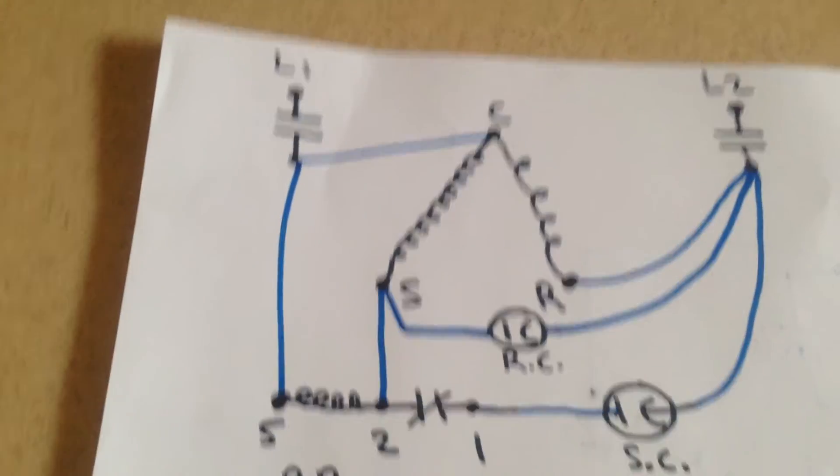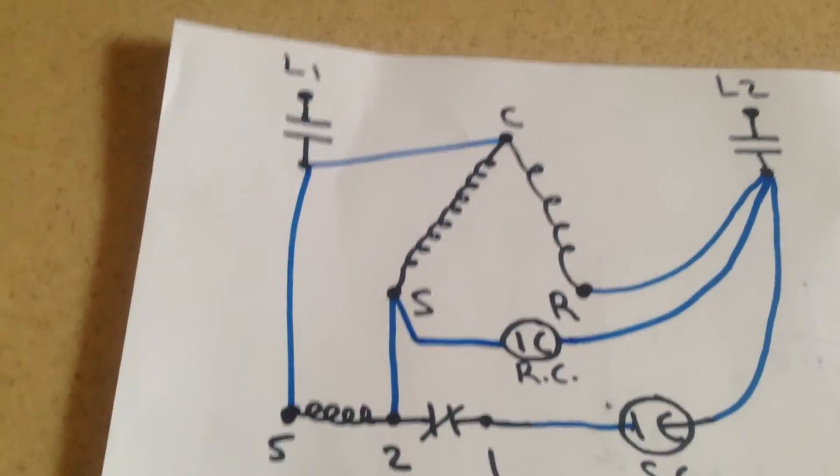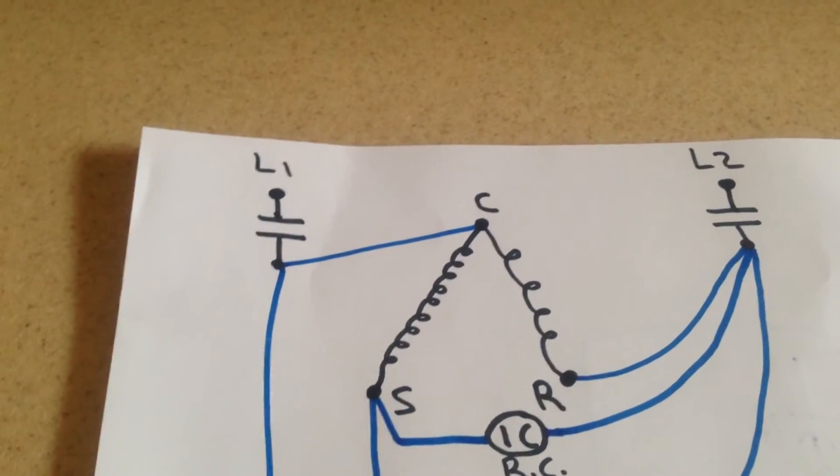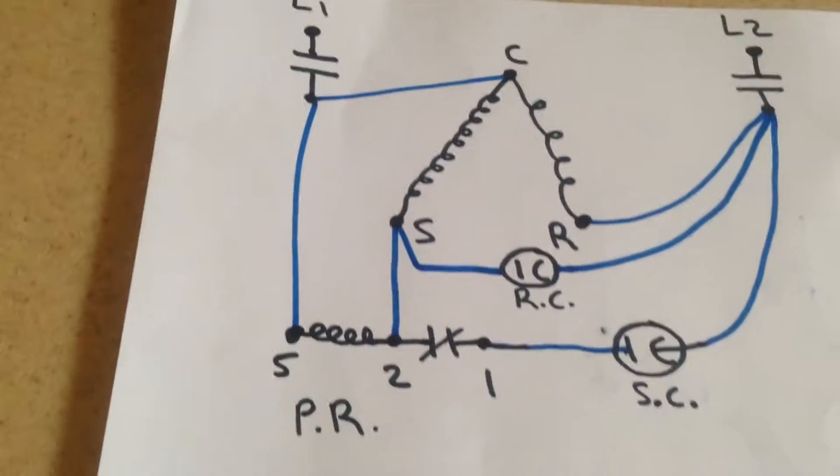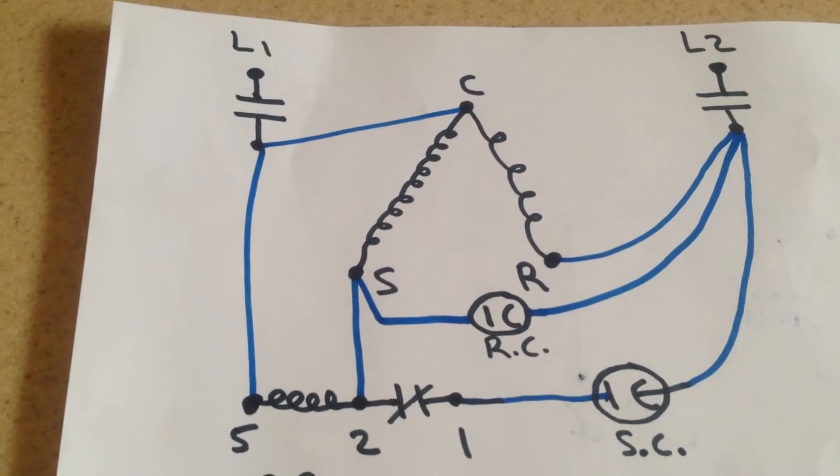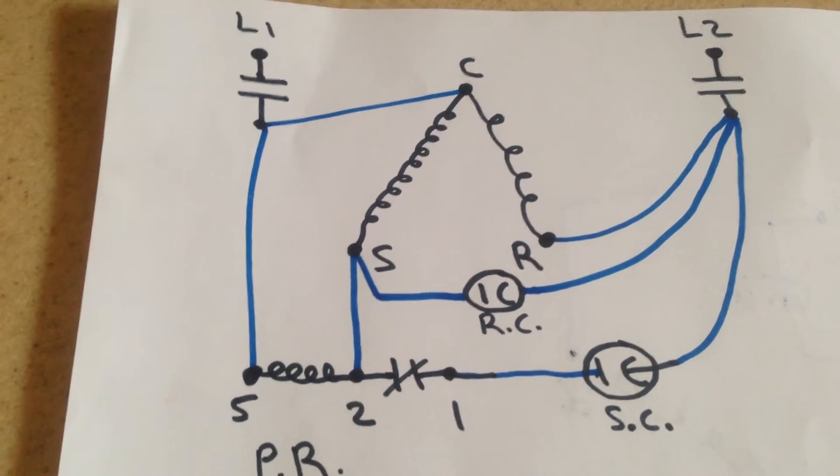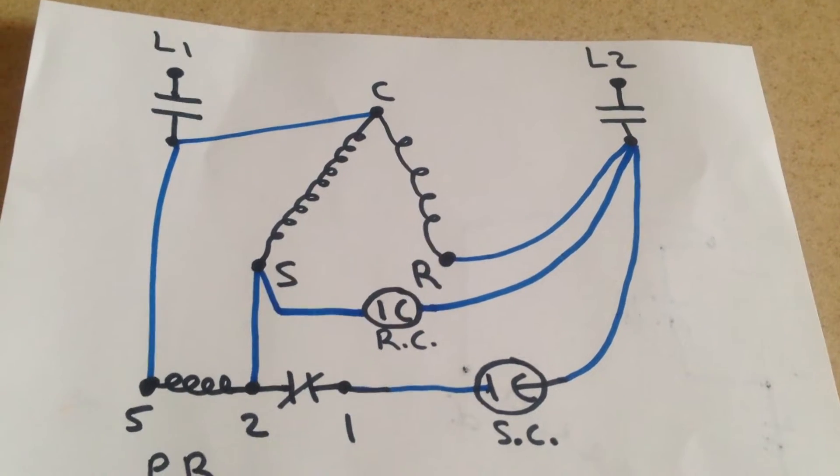And it's going to measure number 5. It's going to be hooked up to the same side as the common on the compressor. Number 2 is going to be hooked up to the same side as the start winding terminal. And number 1 is going to go to the same side as run.